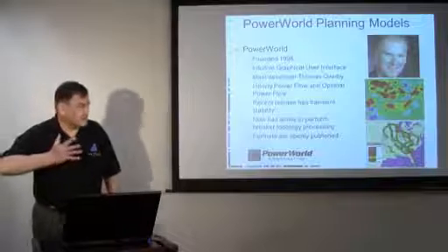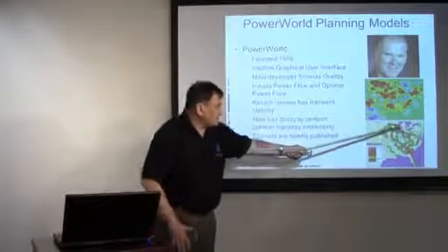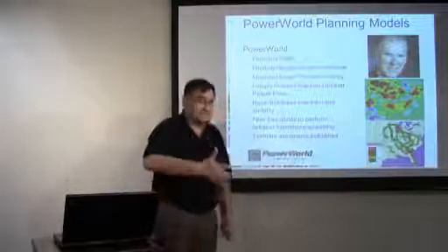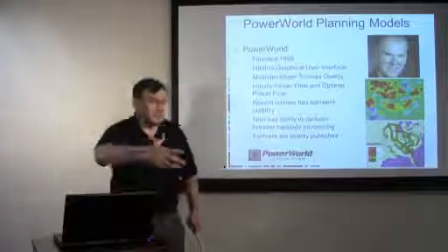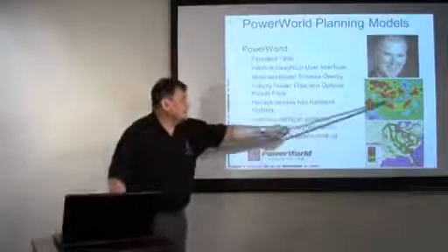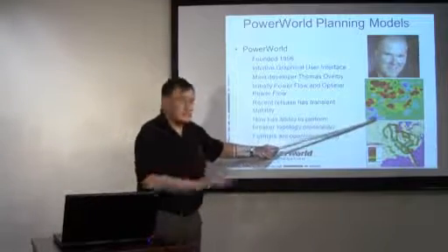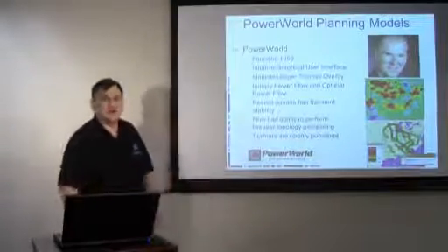Okay, the power just doesn't go on one route. And we talked about this earlier. You may buy a path from here down through here to send 100 megawatts, but really a whole lot of that megawatts goes on other paths where it spreads out. Here's one with contours. This could be a voltage contour. As it goes blue, the voltage is getting into the lower limits. As it goes red, the voltage is exceeding the high limits.